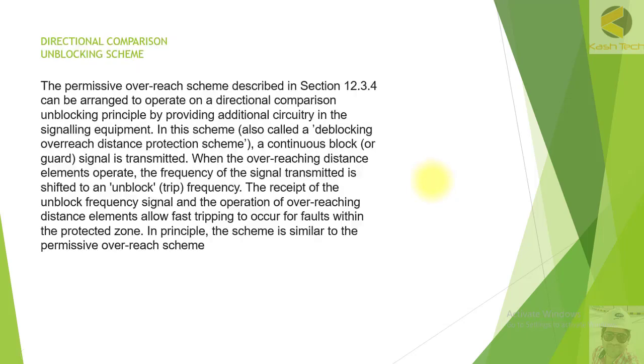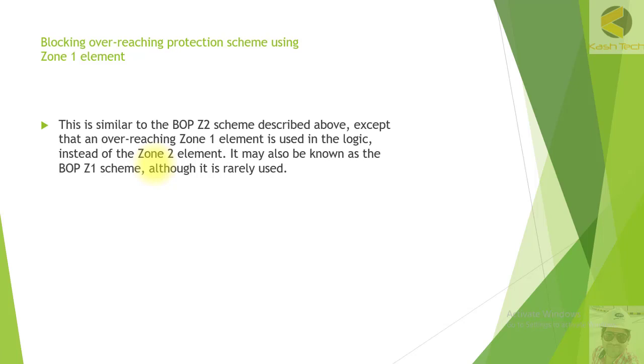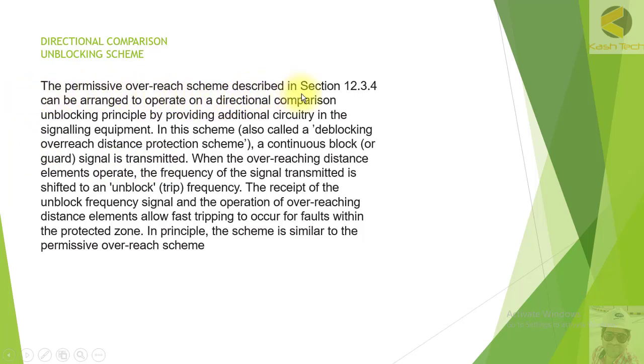Now let's look at the unblocking scheme — the permissive overreach scheme can be arranged to operate on the directional comparison unblocking principle by providing additional circuitry in the signaling equipment. Also called the directional comparison unblocking overreaching distance protection scheme, a continuous block or guard signal is transmitted. When the overreaching distance element operates, the frequency shifts to an unblocked frequency, allowing fast tripping for faults within the protected zone.